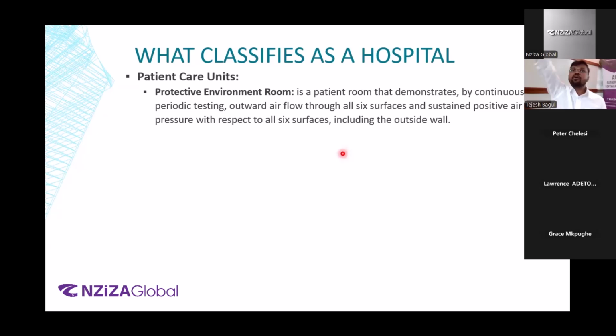What is that? If you are bringing 100 CFM into a room, you are only allowed to have less CFM in the return air duct going back to the air handler. Basically trying to maintain positive pressure. So the air will seep out through the cracks, through infiltration, but it will not come in. Why will it not come in? We don't want outside contaminants coming into the room. All right. That is why we need positive pressurization. But on the other hand, if you are talking about a toilet, in the toilet, we don't want the toilet air coming outside the toilet, right? We want other air to go into the toilet, because the toilet is considered an unclean area. So we need a negative pressure in the toilets.